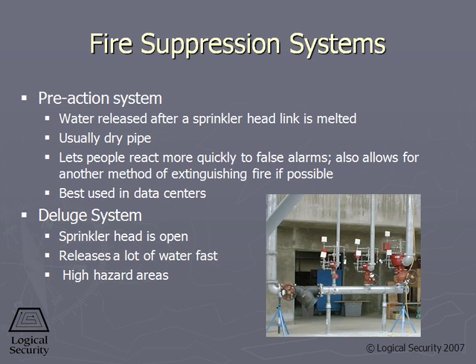So again, we have the dry pipe situation with a plastic billet at the sprinkler head, and only when the alarm sounds, the pipes fill, and then after the billet gets melted due to a specific temperature in the room, that's when the billet melts and releases water in that particular area. Now, the pre-action system is good in minimizing the amount of collateral damage that occurs when the alarm sounds. Only the areas that are exposed to high temperature will have the water damage. So the pre-action system is a little more expensive. Again, it has built-in delays, but it also has something like a conditioned response.